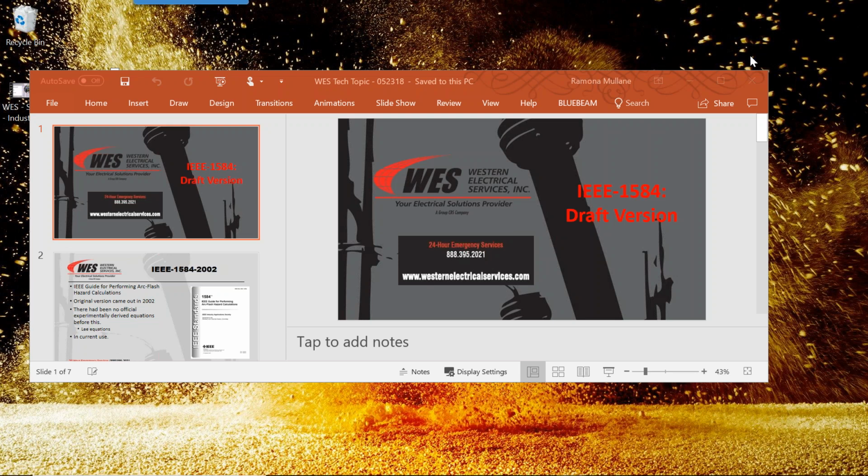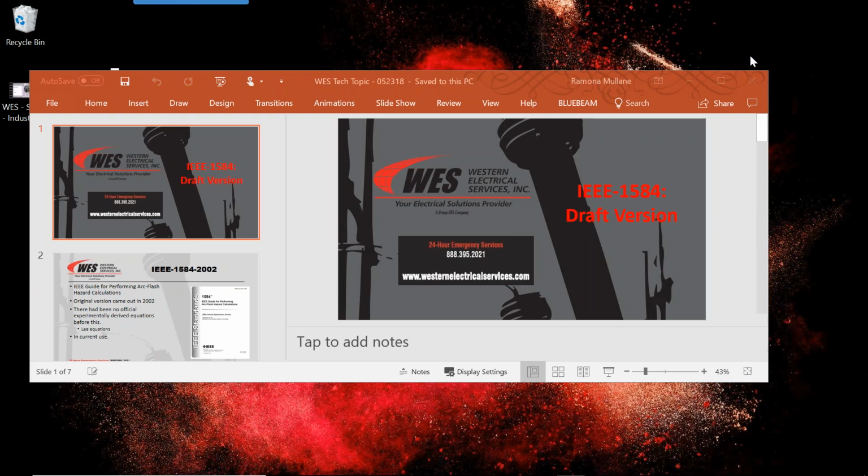Two things I pointed out to the crews at the facility. One, even though you have arc resistive gear that is ideally intended to contain the arc, you still have risks of injury because there are seals that may exhaust out at you. I also mentioned that they needed to still wear required PPE, daily wear type, and in addition, make sure they wore hearing protection.